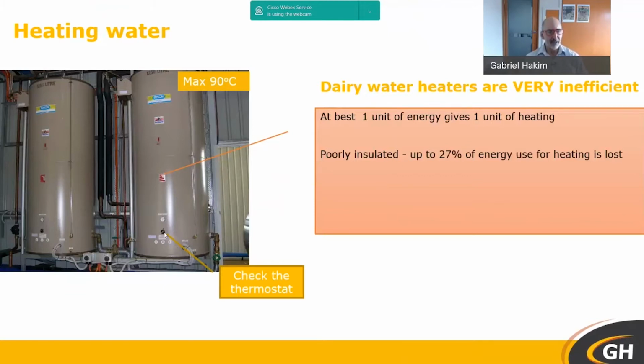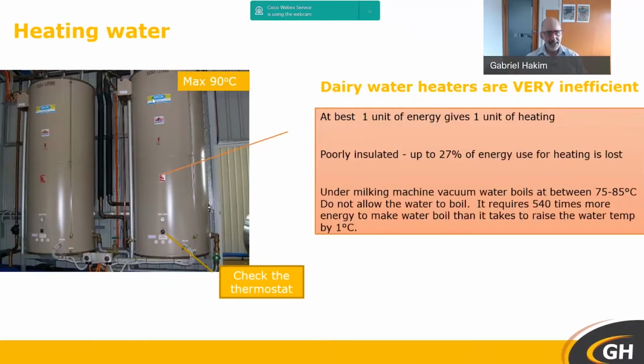A lot of farms, we need to check the temperature. If you're coming out in the morning and you're seeing steam coming out of the top of the dairy, or the heater is boiling, that consumes a whole lot of energy. In fact, to make water boil, you need almost 550 times more energy than you do from getting it, say, from 85 to 86 degrees. So that's a real problem. I see a lot of farms where the thermostat's up to 100. You don't need that. In fact, if you put water into a milking machine at 85 degrees, inside at 50 kPa, the water will boil and steam will be generated, cleaning performance will be reduced, and you'll damage the vacuum pump.